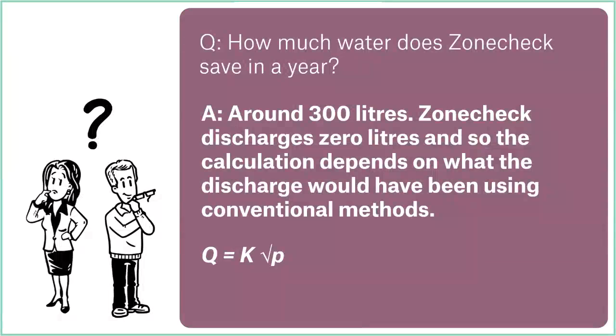It also depends on the size of the test valve. So how big is the opening in which the water's coming out? Remember, that is measured in K factor. Now the test line should be sized for one sprinkler head in operation. So if you've got K80 sprinkler heads, there should be a K80 orifice on that test outlet. If you've got K115s, it should be a 115. If you've got 160s, it should be 160. So again, we're just going to take an average. Ordinary hazard sprinkler systems might have 115 heads on them, so we could use that. But 160 is the biggest, so we can use that figure as well.